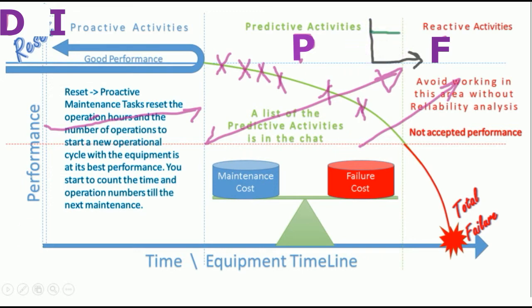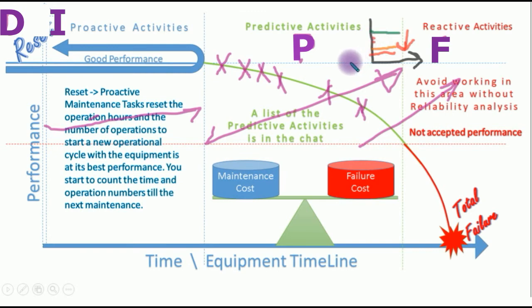The alarm condition will come here, and the trip condition or total failure condition will come here. So you have a margin already. If you can detect any change in this margin — working a little bit down here — if you can detect this from the pressure and flow measurement tools you have, you can simply take it on a screen in the operation room, make some trending for it, find that your pressure is falling a little bit, and then go and inspect. That's free — you already have sensors installed in the field that convey to you the status of the equipment.